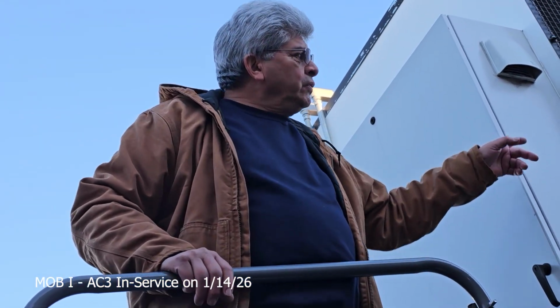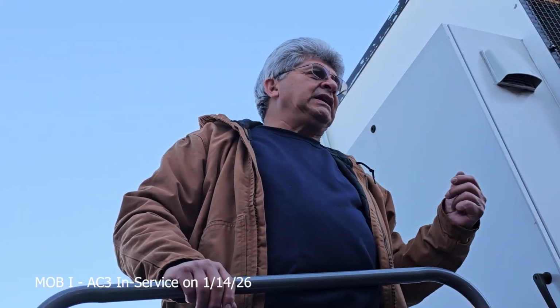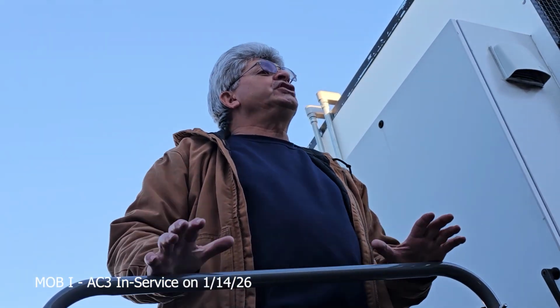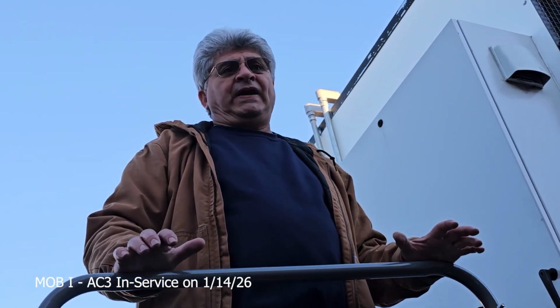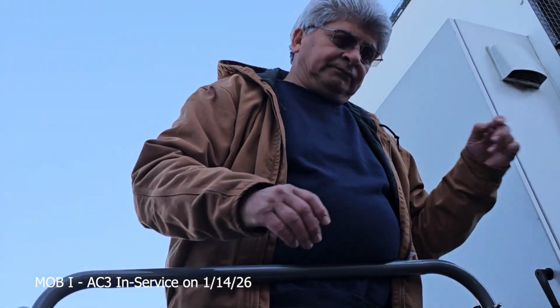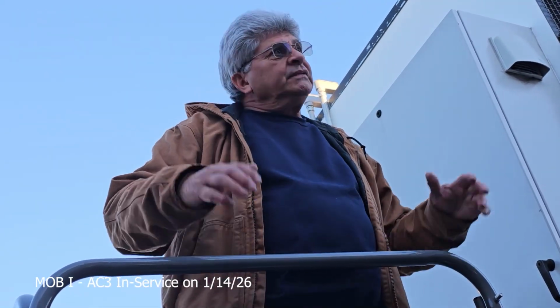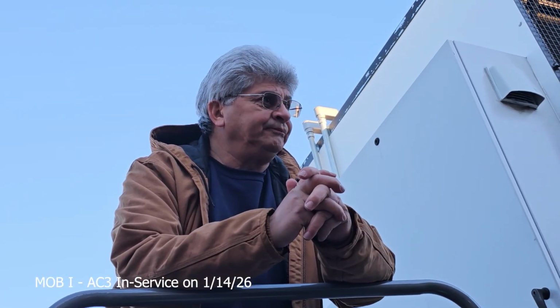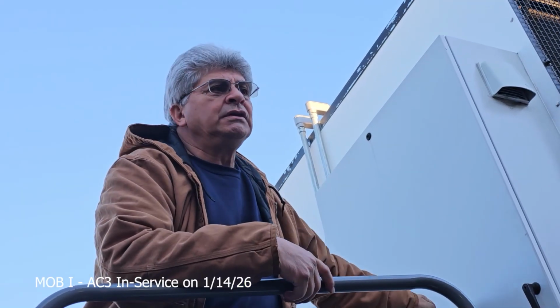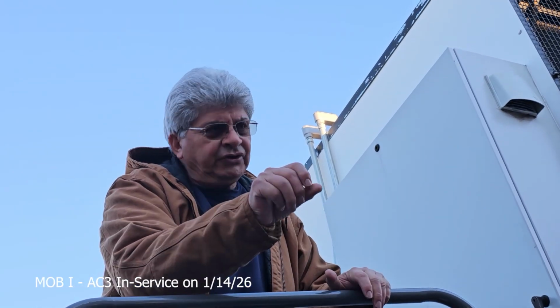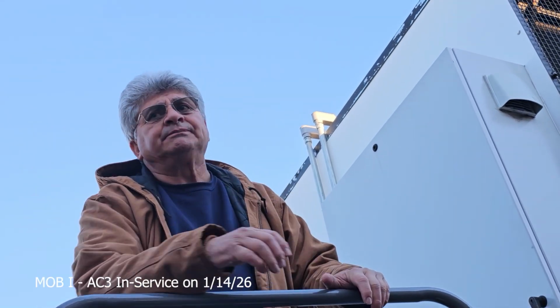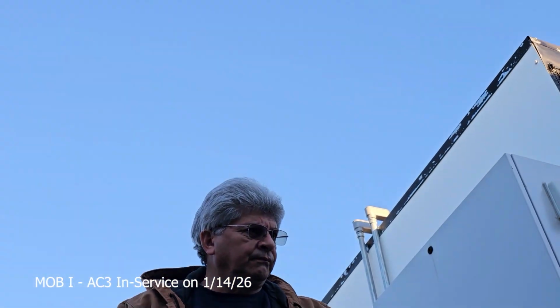You open that door, you're doing your check, that should be part of your normal check. Check your fans. You see that little red light on? The fan's not going to be running if the light's on. So you know the fans shut down. We're going to come back here for 7. That requires you to shut the MSP off in here, turn it off, and back on again. Just for that fan or all the fans?